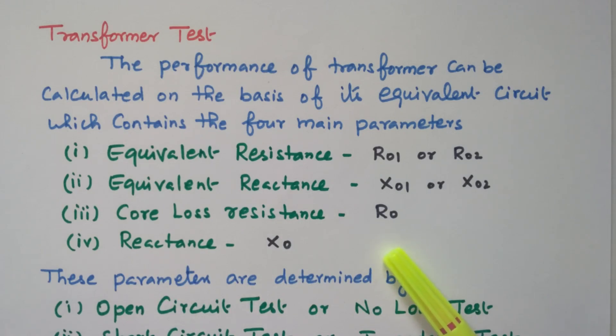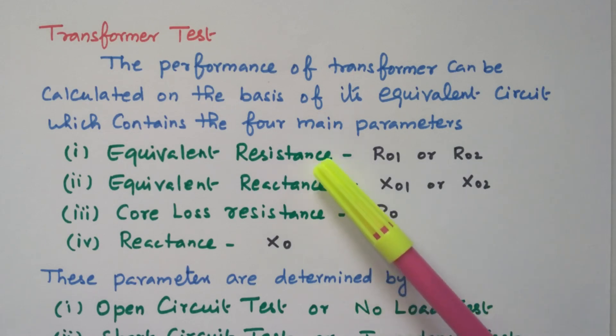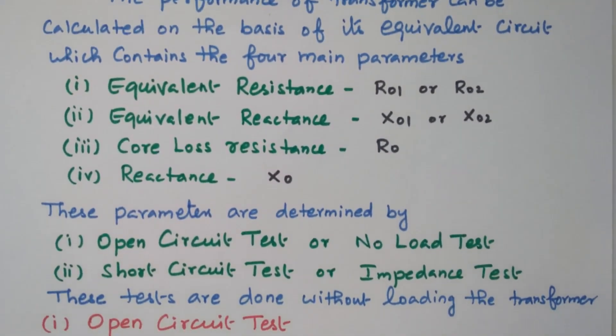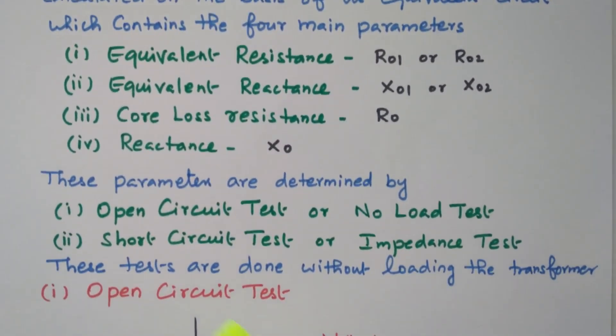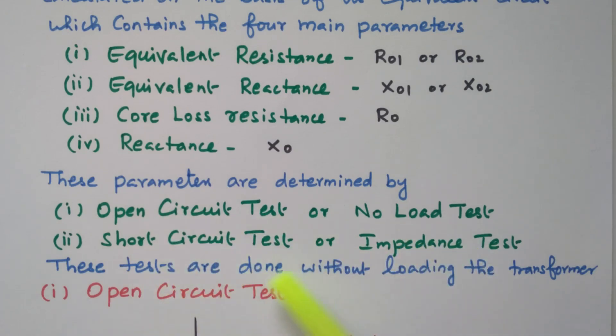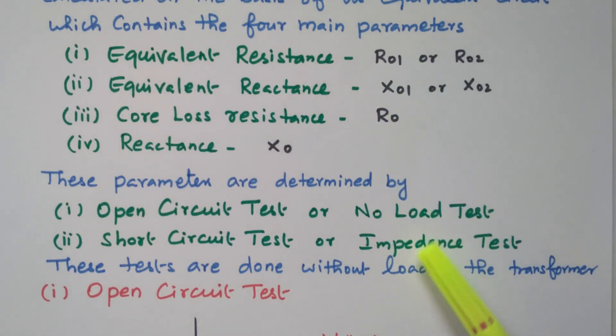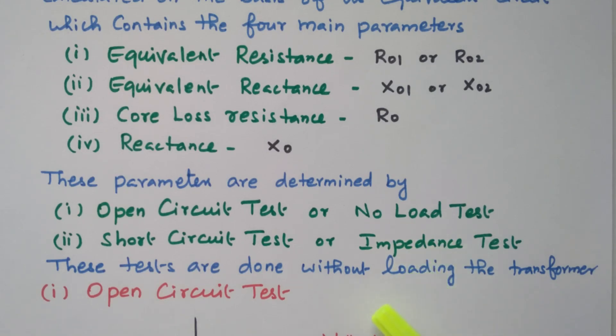From the equivalent circuit, we can analyze the performance of the transformer. To identify these four parameters, we need to perform the transformer test. There are two types of tests available: the open circuit test (or no load test) and the short circuit test (or impedance test). These four parameters are calculated from these two tests.